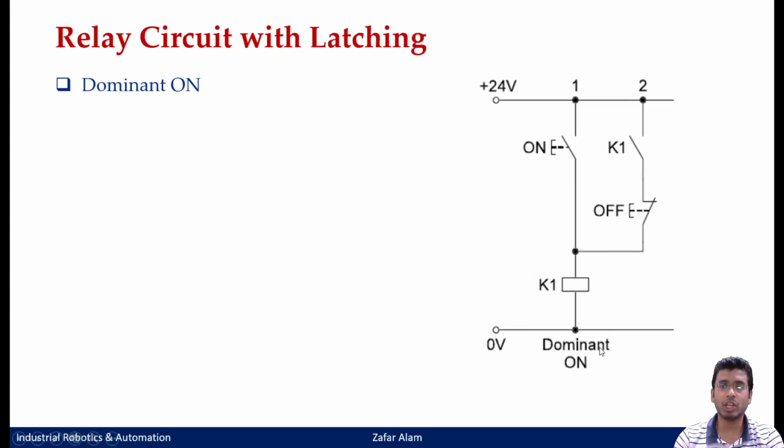Fine. Now imagine if you press both the switches together, what would happen? Will the relay work as a latch, or will the relay not switch off? What will be the case? If I press both the on and off push button together, then what would happen? This circuit would break. Why? Because this is a normally closed circuit, so whenever it is actuated, it will break the circuit.